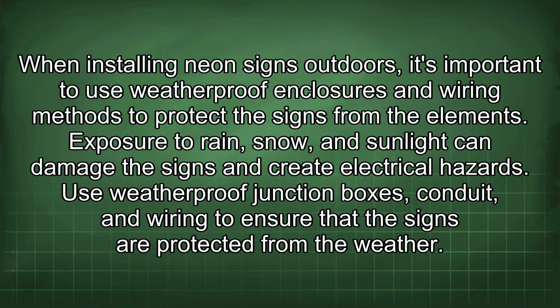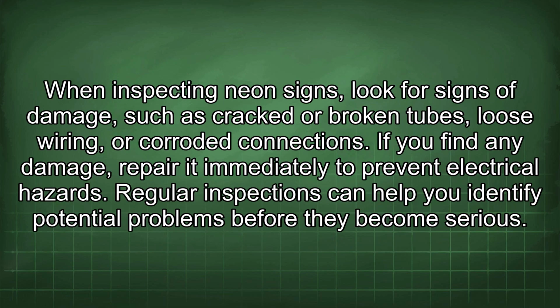When installing neon signs outdoors, it's important to use weatherproof enclosures and wiring methods to protect the signs from the elements. Exposure to rain, snow, and sunlight can damage the signs and create electrical hazards. Use weatherproof junction boxes, conduit, and wiring to ensure that the signs are protected from the weather. When inspecting neon signs, look for signs of damage, such as cracked or broken tubes, loose wiring, or corroded connections.